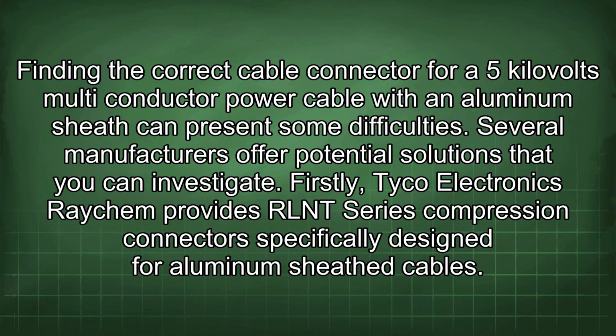Finding the correct cable connector for a 5 kV multi-conductor power cable with an aluminum sheath can present some difficulties. Several manufacturers offer potential solutions that you can investigate. Firstly, Tyco Electronics can provide RLNT series compression connectors specifically designed for aluminum sheathed cables.